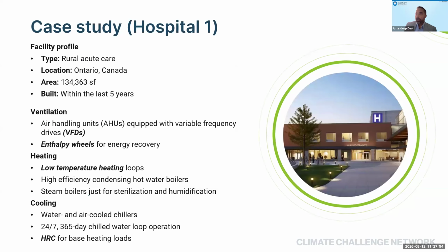So the case study 1, it's hospital 1, which is a rural hospital in Ontario, Canada, one of the provinces. It's about 130,000 or 150,000 square feet, and was built in the last 5 years. With all of these hospitals, the infrastructure was what you would expect in a new hospital to be top of the line. In the ventilation systems, the air handling units were equipped with variable frequency drives to enable setbacks. There were enthalpy wheels to enable heat recovery on the ventilation exhaust.